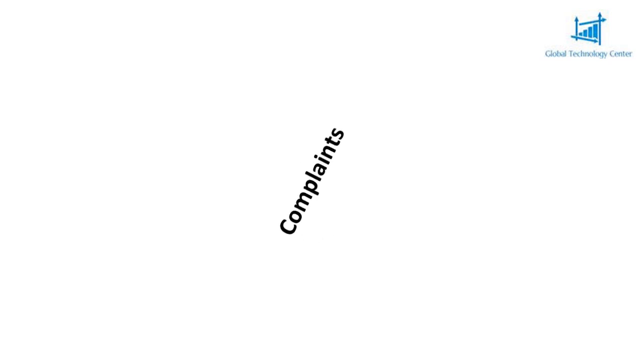While the old ISO 13485 standard discussed the need to handle complaints, this important material was spread over several sections. The new standard brings most of it together in one new section and broadens and expands it to include all kinds of complaints, not just customer complaints. It now also expects you to develop and document complaint handling procedures that comply with all applicable regulatory requirements. The old standard merely asked you to establish arrangements, not procedures.